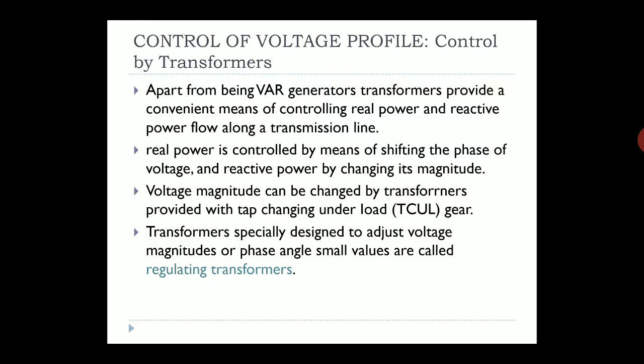The voltage magnitude can be changed by transformers provided with tap-changing under load (TCUL) gear. The voltage is directly proportional to the reactive power, so it can control the reactive power. Transformers specifically designed to adjust the voltage magnitude or the phase angle by small values are called regulating transformers.